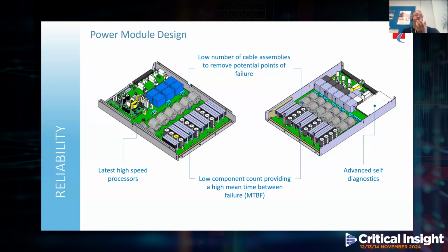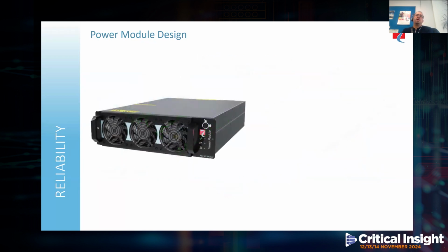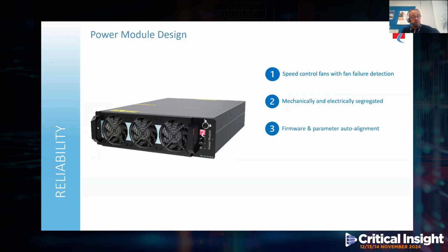And the modules use the very latest in high-speed processors and advanced diagnostics. In addition to this, the modules use speed control fans to minimize wear and tear, along with fan failure detection. They have been designed specifically to enable the fans to be easily changed. As with all UPS systems, the fans will typically operate on an average of 7 to 9 years, at which point they'd have to be changed. But depending on the conditions and load, these fans can actually last for the full 15 years, thus reducing component wastage and servicing costs. The module is mechanically and electronically segregated, preventing fault propagation between modules.